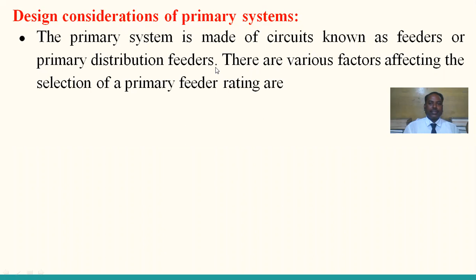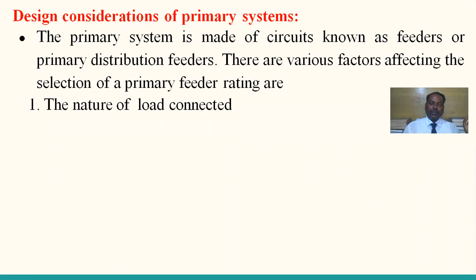There are various factors affecting the selection of primary feeder rating: the nature of load connected, the load density of the area served, the growth rate of the load, the need for providing spare capacity for emergency operations, the type and cost of circuit construction employed, the design and capacity of substation involved, the type of regulating equipment involved, the quality of service required, the continuity of service required.